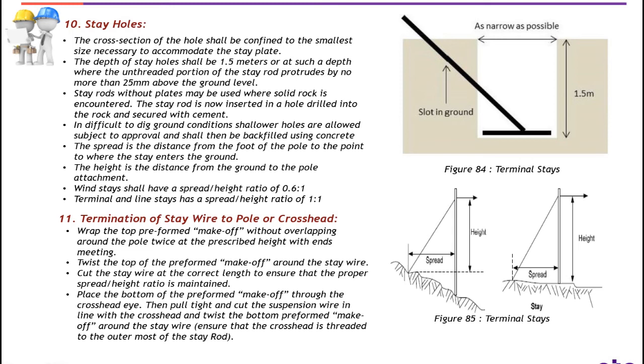Termination of stay wire to pole or crosshead. Wrap the top preformed make-off without overlapping around the pole twice at the prescribed height with ends meeting. Twist the top of the preformed make-off around the stay wire. Cut the stay wire at the correct length to ensure that the proper spread-height ratio is maintained. Place the bottom of the preformed make-off through the crosshead eye, then pull tight and cut the suspension wire in line with the crosshead, and twist the bottom preformed make-off around the stay wire. Ensure that the crosshead is threaded to the outermost of the stay rod.